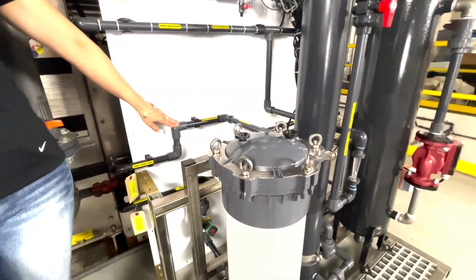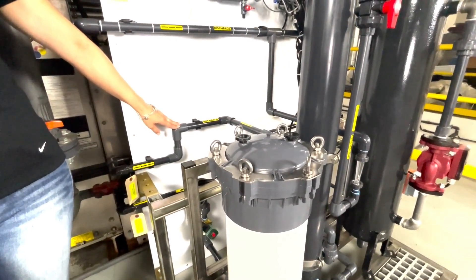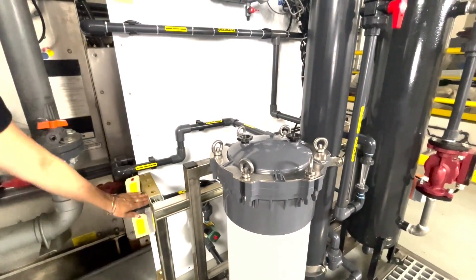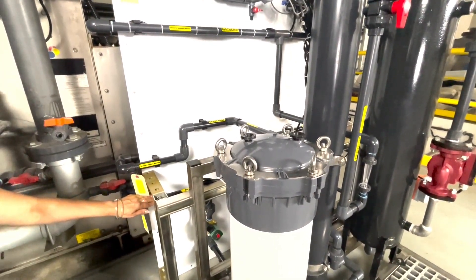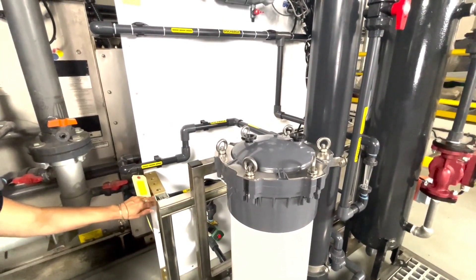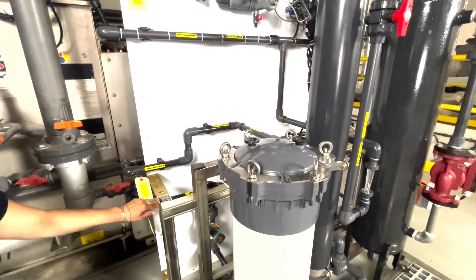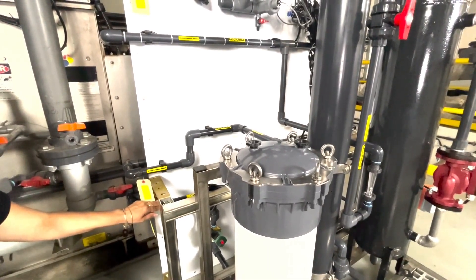This connection is your discharge line for your oxidizing biocide out of the brominator. Lastly, this connection point is the inlet connection for your brominator. Dover recommends the use of city water as source water, but cooling tower recirculation water may be used as an alternative.